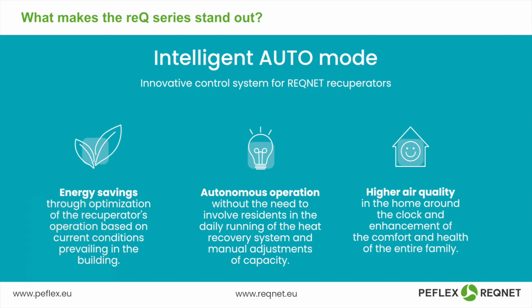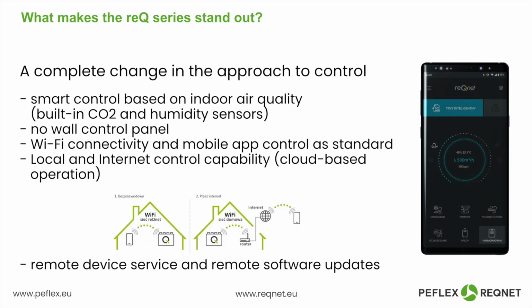Intelligent control system. The intelligent control system allows the ventilation unit to operate autonomously, which, among other things, translates into the quality of the air inside the building, but also into energy savings, so that the proper operating parameters are maintained inside the building. And just like here, for example, in our REQNET units, whether it's the REQ series or the ISI series, we have the option of intelligent control, meaning that based on air quality, the device automatically adjusts its performance in terms of airflow to maintain those parameters at an optimal level. There's also the option to control it via an app that works with the recuperator over Wi-Fi. And here we have these two options, either direct control or control via the internet, meaning connecting the unit to the router and being able to manage it that way.